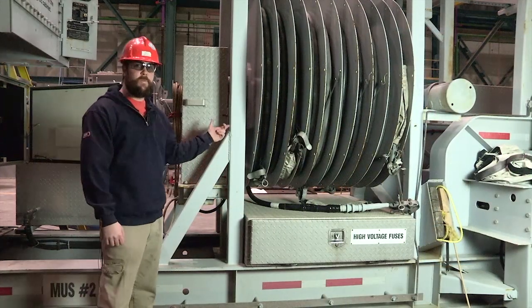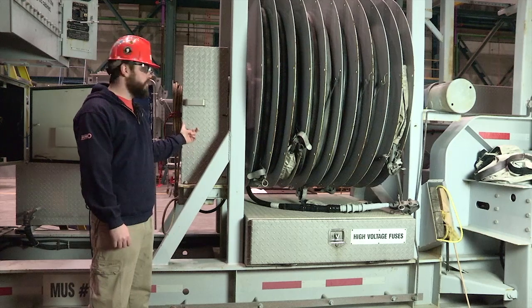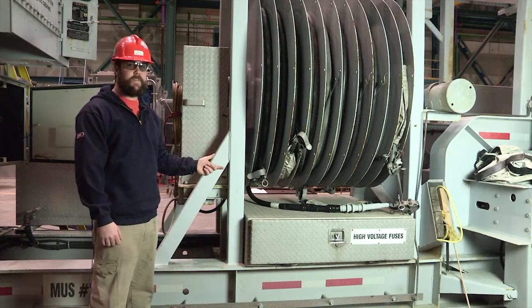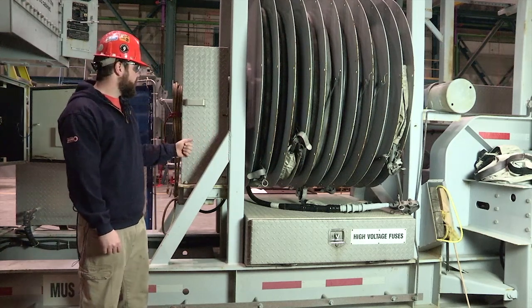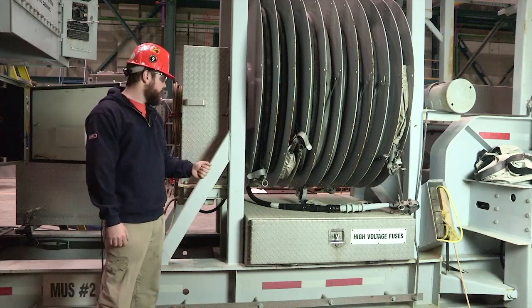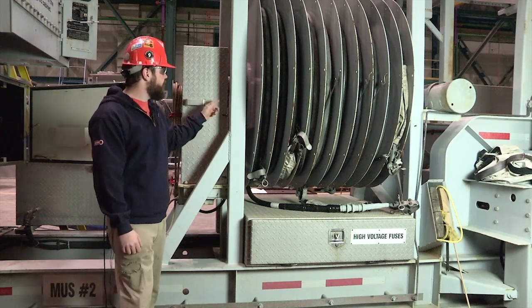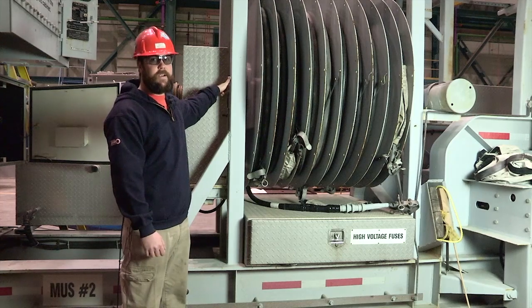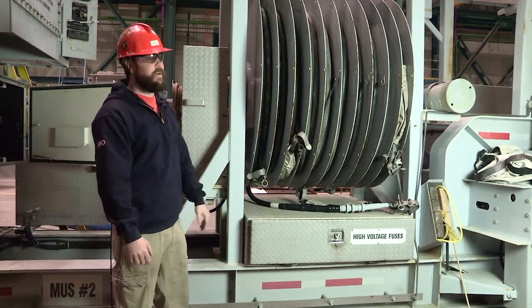Next, we're going to move on to the cable reel, and what you want to do here is remove this cover. It's good to inspect the chain and the transfer case on the electric motor. Just make sure everything's greased, everything's topped up, and just inspected. The other thing too is that you've got grease fittings on both bearings on your cable reel. You want to grease those for sure.